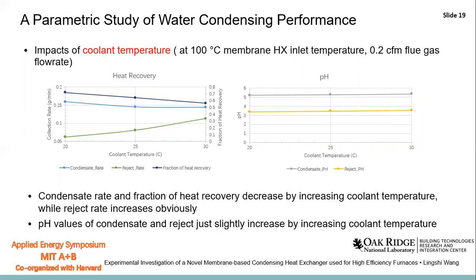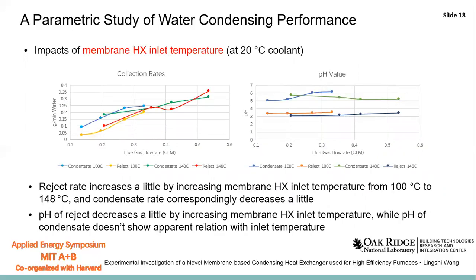These two figures show the impact of membrane heat exchanger inlet temperature. It can be seen that the reject rate increases slightly with increasing membrane heat exchanger inlet temperature from 100°C to 148°C, while the condensate rate decreases slightly. No apparent relationship was found between the pH value of the condensate and the inlet temperature of the heat exchanger.